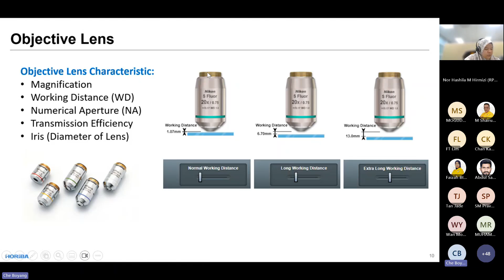For the Horiba Raman microscope, our latest model has a very unique feature, and I think it's very helpful for your normal operation. Currently, when you change the objective lens, the user has to manually change the parameter inside the software to tell it whether you're using the 10x or the 100x objective lens. Then all the parameters will be adjusted accordingly, and you will see the correct scale bar.